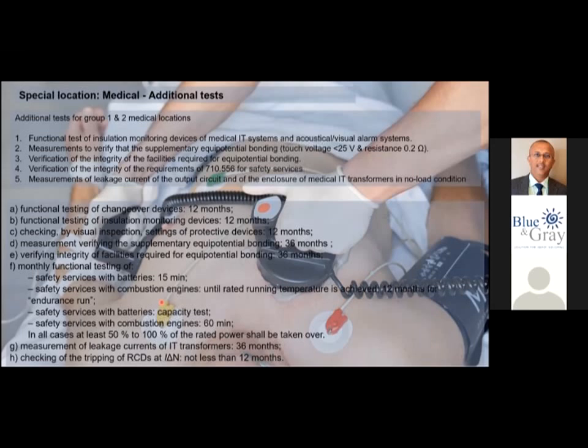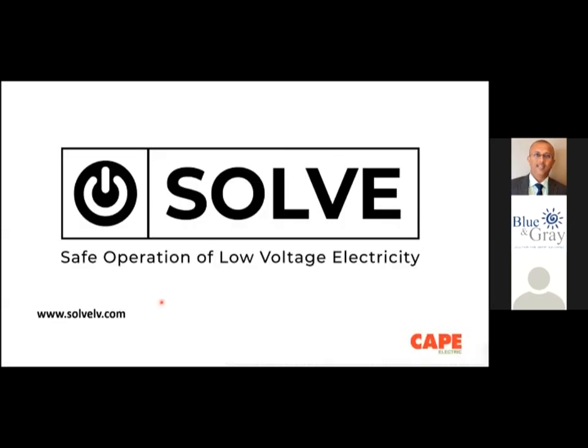So basically, testing or verification or audit of a low voltage electrical installation is not about testing the earth electrode resistance. Actually, earth electrode resistance testing has been removed from the standard. Not a few years back, in IEC it was about 20 years back. You don't need to do an earth electrode resistance test in a low voltage electrical installation, because the earth electrode doesn't have any influence on your installation with respect to safety or reliability, except for lightning protection.